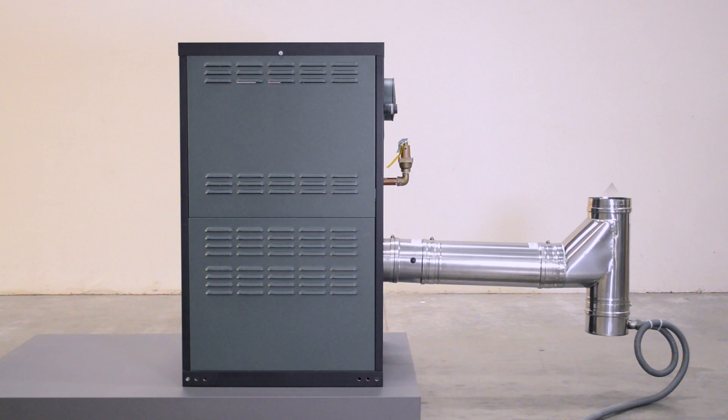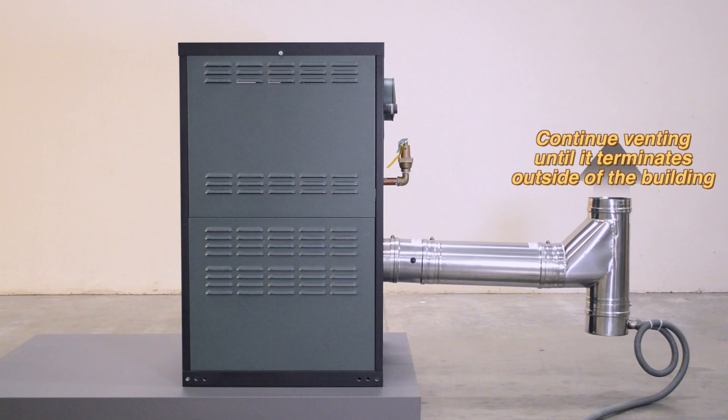Continue installing the remainder of the vent material until it exits the building. Be sure the vent complies with the National Fuel Gas Code. Spacers must be used when penetrating walls and ceilings. Any horizontal run of vent pipe must be supported a minimum of every 5 feet.